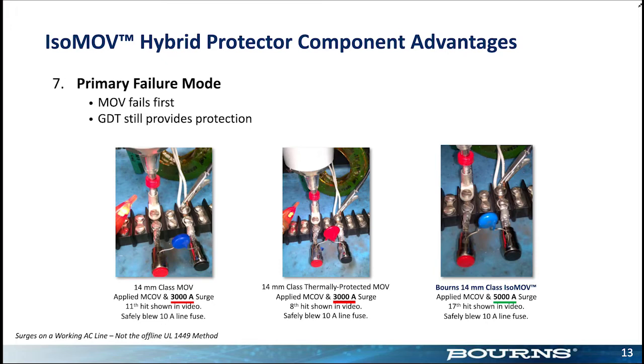Quite impressive. On the middle one, we took the thermally activated fuse, and again, we surged it at 3 kA. Finally on the 8th hit, it blows. But it blew our inline fuse, which says the thermal fuse did not activate, which is somewhat of a surprise. And I'll get back to this after the movie. And then the third one, first of all, we couldn't get it to blow at 3 kA. We had to bump it up to 5 kA. And on the 17th hit, it finally did. You'll see a little, not nearly as impressive as the other two, just a little pinhole thing. I use the word pinhole. I'll discuss that in a minute, because I said they don't do pinholes. But we'll discuss that in a second. So let me show this movie.